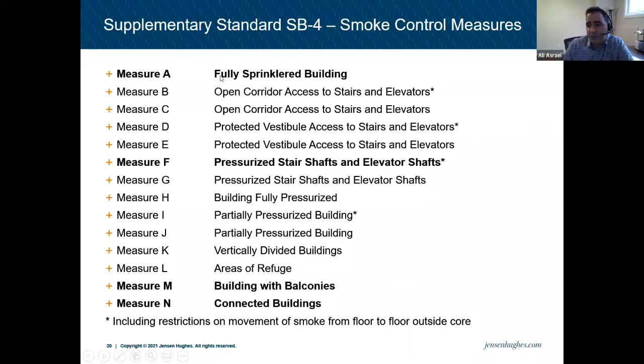So measure A is applicable to fully sprinklered buildings. A lot of new buildings that you see these days, a lot of residential buildings, are required to be fully sprinklered now, and this measure applies to them. And measure F is another one you see for a lot of older existing buildings, where the building at the time was not sprinklered, or is not sprinklered even now, and it's a lot of residential occupancies. You see pressurized above grade stairs, elevator shaft, and all that.